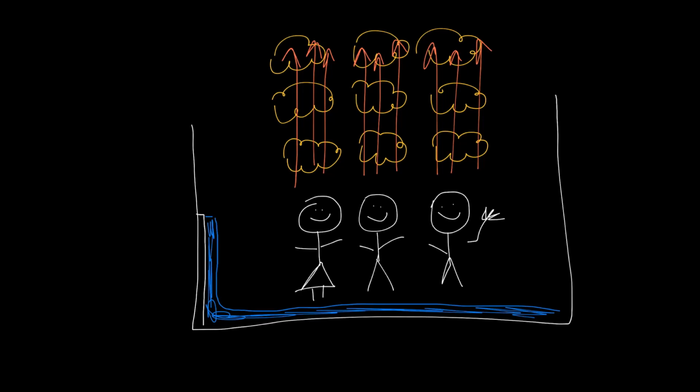There are certain rules of thumb for the design of displacement systems. First of all, the displacement diffusers should be selected for an average face velocity between 40 and 70 feet per minute. Since the air is discharged directly into the occupied level of the space, a supply air temperature between 60 and 65 degrees Fahrenheit is generally recommended. However, lower supply air temperatures may be employed when the displacement application involves transient occupants.